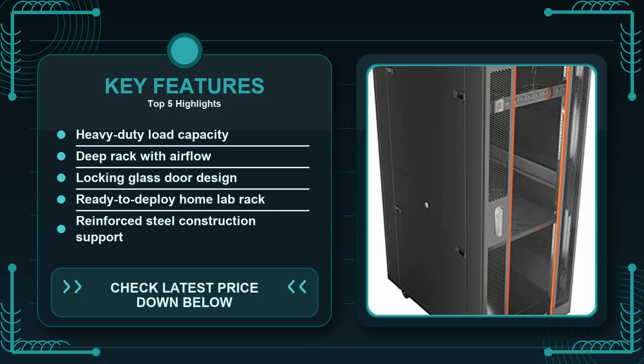However, the glass does have a trade-off. When you close the door, you lose a bit of direct airflow, so you'll rely more heavily on the built-in fans to pull hot air out the rear. The included fans are decent, but they aren't industrial grade. In a densely packed rack with several high-power servers, you'll likely need to add a supplemental exhaust fan or place the cabinet in a well-ventilated corner.